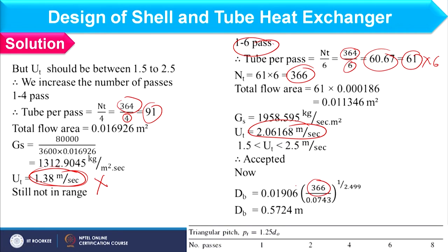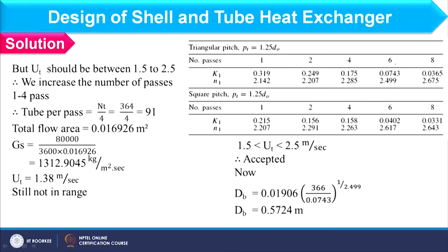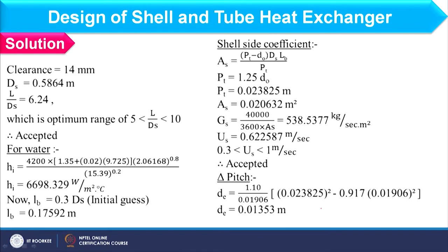Since the passes have changed, bundle diameter and shell diameter will also change slightly, along with the number of tubes. We must again ensure L/D falls within the permissible range. Considering 366 tubes and 6 passes, K1 and N1 values are obtained from the table. Bundle diameter comes as 0.57 m. Clearance from the same graph comes as 14 mm. The L/D ratio is 6.24, which is within the range.